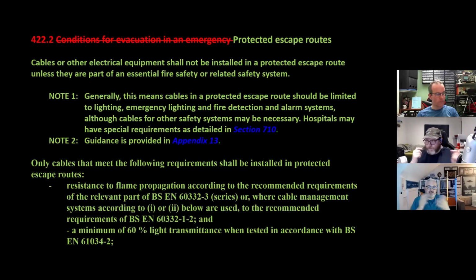So this is what fire engineers are great at, by the way - they're excellent at giving really pragmatic advice. There is an Appendix 13 that gives more guidance, some decent guidance in there, but it states only cables that meet the following requirements shall be installed in protected routes: resistance to flame propagation according to the relevant parts of 60332-3, or where cable management systems according to 1 or 2 below are used, to the recommended requirements of BSEN 60332-1-2, and with a minimum of 60% light transmittance.